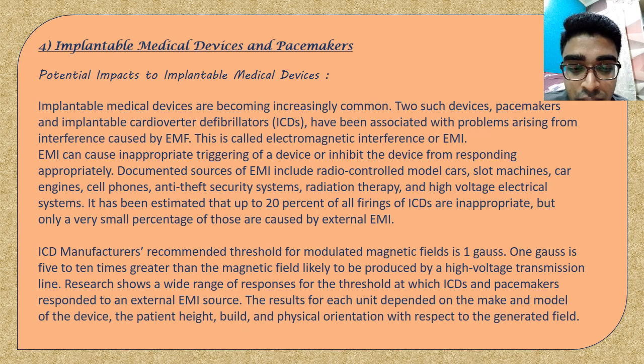The ICD manufacturer-recommended threshold for modulated magnetic field is 1 Gauss, which is 5 to 10 times greater than the magnetic field likely to be produced by a high voltage transmission line. Research shows a wide range of response thresholds at which ICDs and pacemakers respond to an external EMI source.